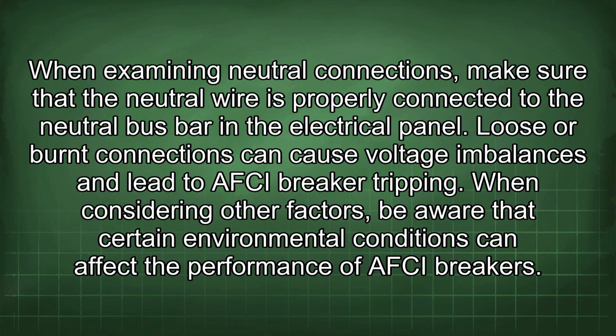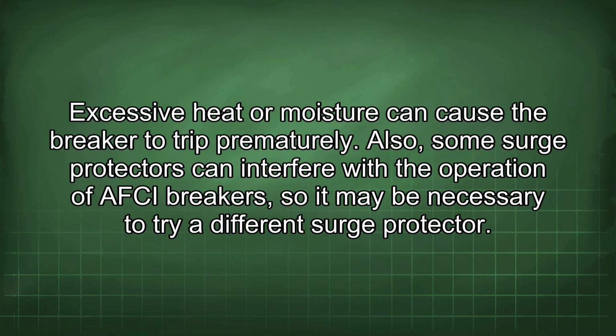When examining neutral connections, make sure that the neutral wire is properly connected to the neutral bus bar in the electrical panel. Loose or burnt connections can cause voltage imbalances and lead to AFCI breaker tripping. When considering other factors, be aware that certain environmental conditions can affect the performance of AFCI breakers. Excessive heat or moisture can cause the breaker to trip prematurely.